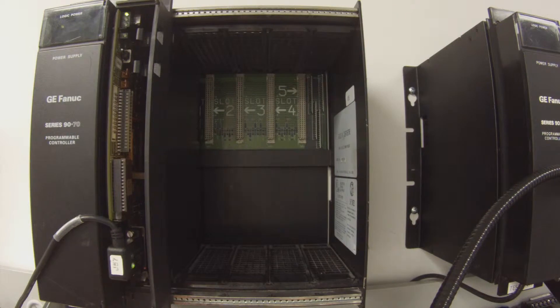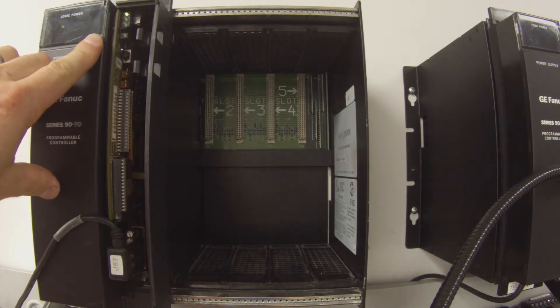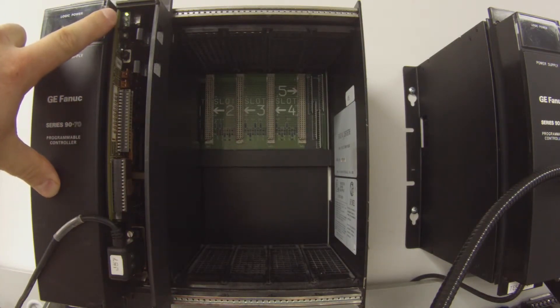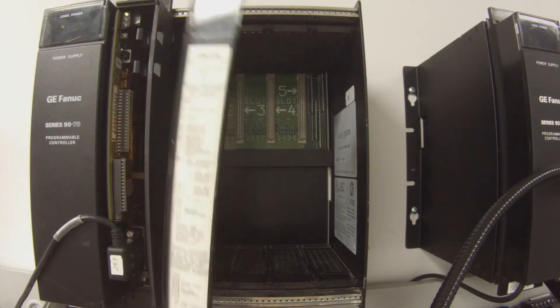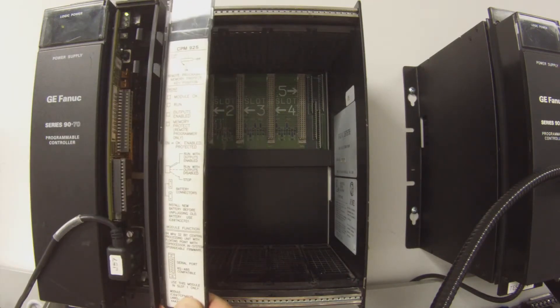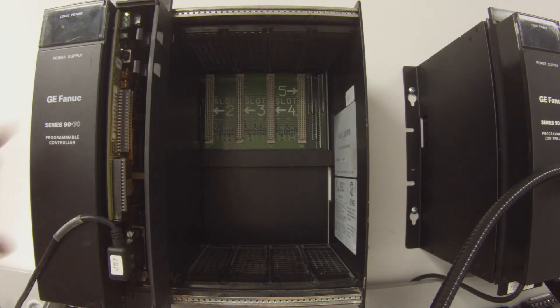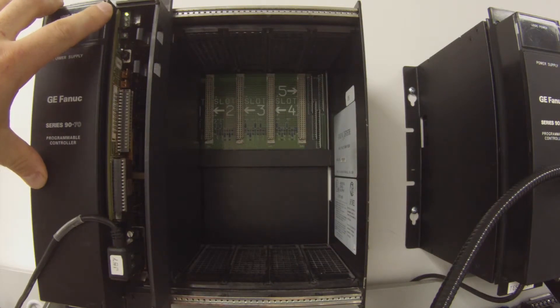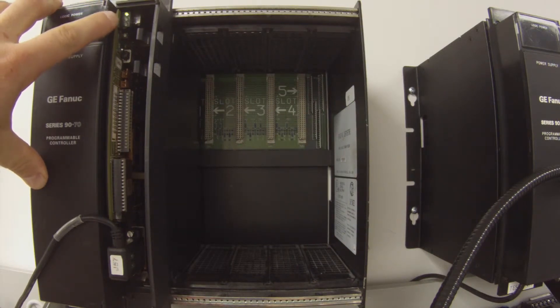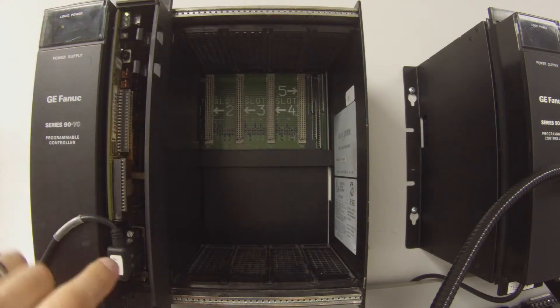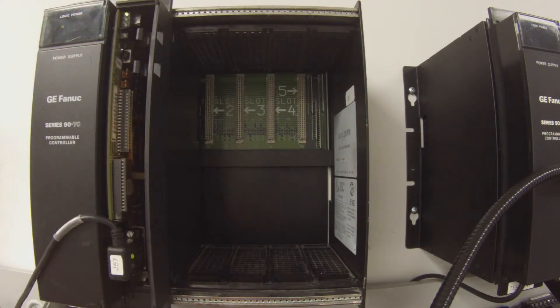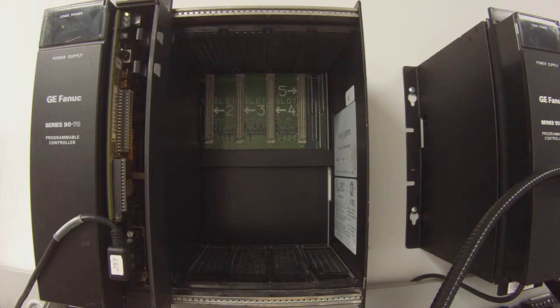First thing I want to indicate to you if you're testing your processor is this LED here. I have the door off just so it's not distracting for our test, but the door has information on what these different LEDs are. The first one is module OK and mine is solid, which is good. If for any reason you don't have this light on or it's blinking and you can't communicate, then that means there's definitely a large error, a big problem with your processor and you won't be able to follow this test. You'd have to stop right now.